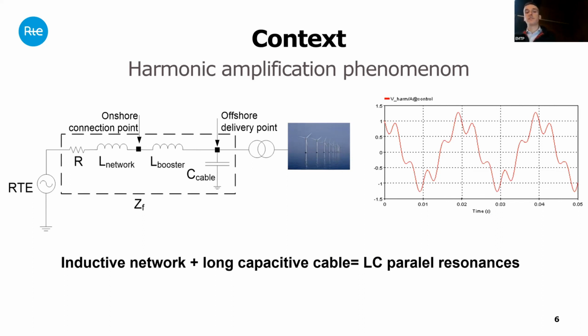With long capacitive cables, we can have LC parallel resonances which can amplify the harmonic background. So the main objective of our studies is to estimate how the harmonic background voltage will be amplified by the connection.